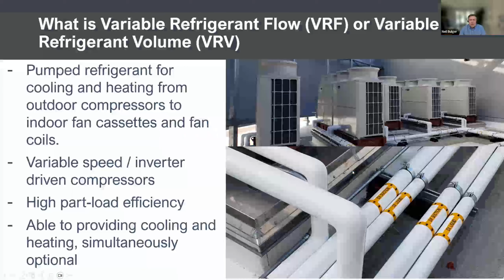All right, so what is VRF? Variable refrigerant flow, or variable refrigerant volume, is sometimes another term that's used for these products. It's a type of pumped refrigerant, so we're moving refrigerant around a building. There's outdoor compressors where the refrigerant is often made very cold or very hot, and then it's pumped through insulated pipes into the building, either as a liquid or a gas, to different rooms. Almost all VRF systems are variable speed inverter driven compressors. That's the critical piece that makes these efficient and puts them out ahead of other heat pump products on the market. There are definitely inverter heat pumps in other products, but almost all of VRF is inverter driven.